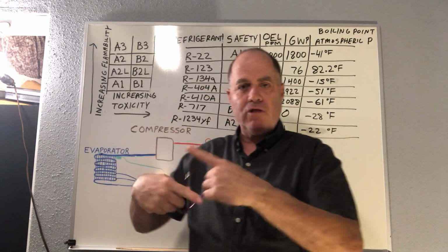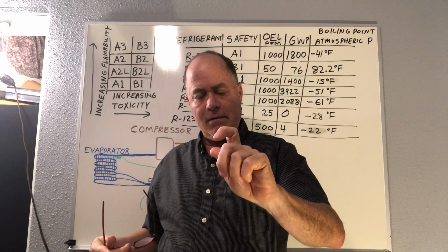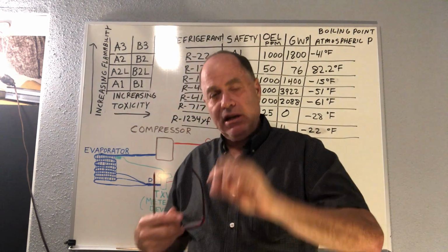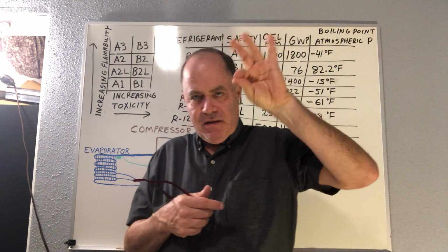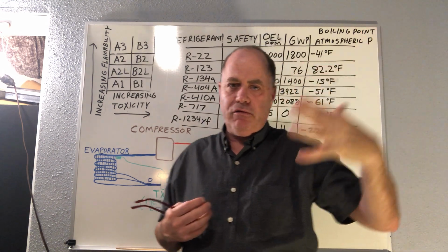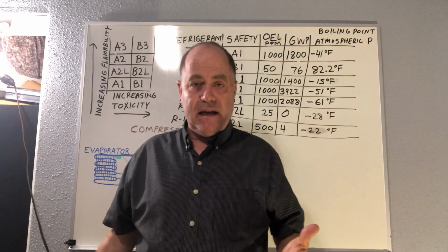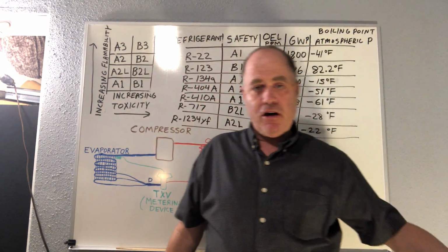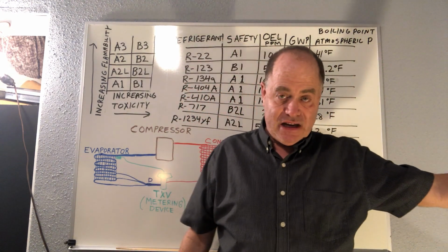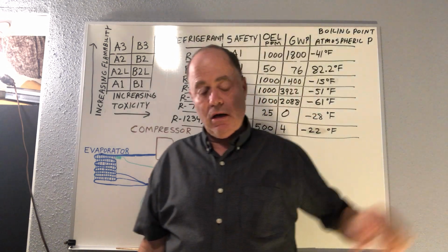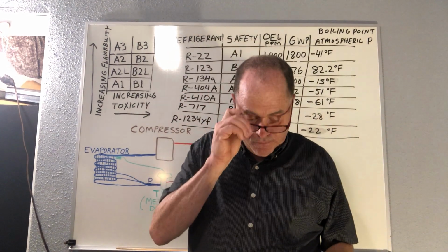Through a couple of filter dryers, and then the oil would come out the bottom, any oil that was in the refrigerant, and then any tiny bits of air could be discharged off the top of it, so that the refrigerant, you did quite a bit to clean it up. And then we have reclaimed refrigerant, where you take it back to a parts house where it can be brought back to a new standard. And they'll take care of that for you.